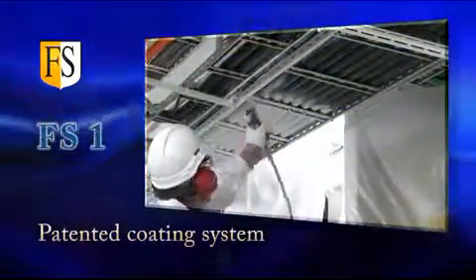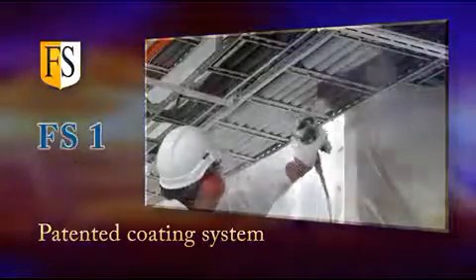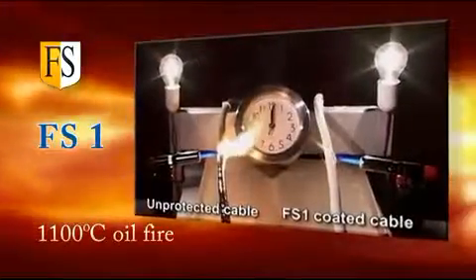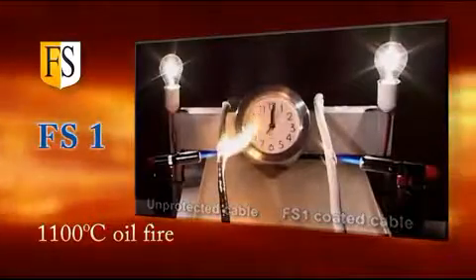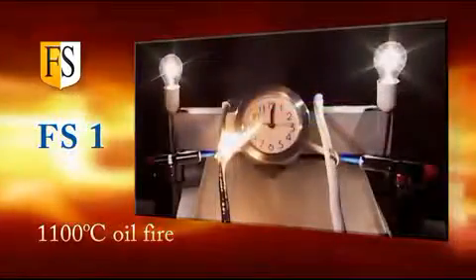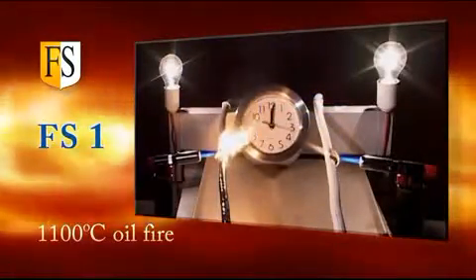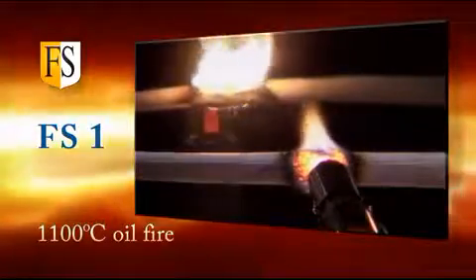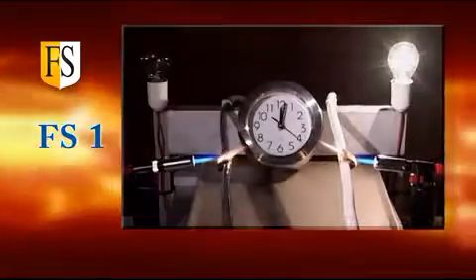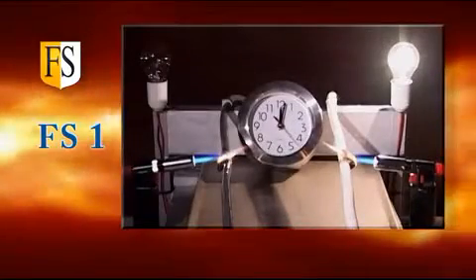The patented FS1 coating system has been tested on an 1100 degrees Celsius oil fire for more than 1 hour without any problem to the insulation or the electrical properties. Normal cables, such as flame retardant and fire resistant cables, cannot withstand such a fire, and vital cables are often routed through high-risk areas. As we can see in this test, a short circuit has occurred in the unprotected cable after less than 2 minutes.